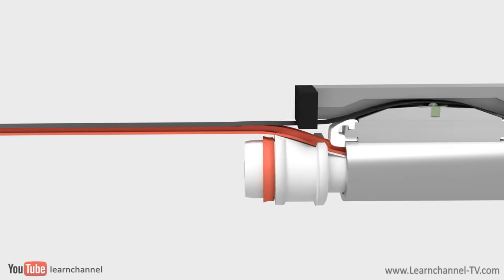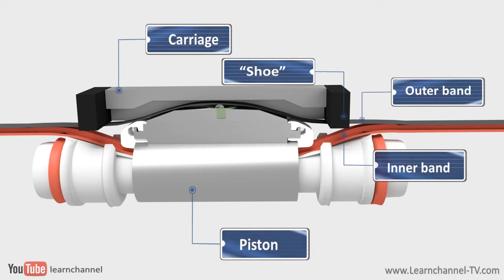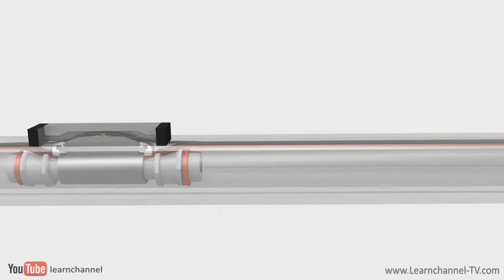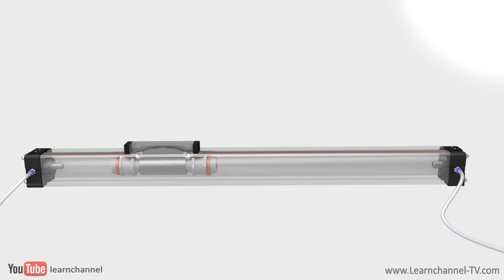As the piston drives, the two-band sealing strips open in front and then close behind, regardless of the direction of travel. The seals of the piston inside the cylinder barrel press the inner band tightly against the barrel of the cylinder, preventing air leakage. The outer band is pressed tightly against the outside of the slot of the cylinder barrel with the so-called shoes of the carriage.